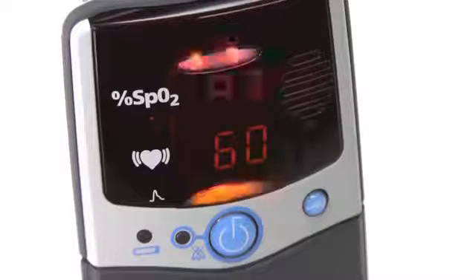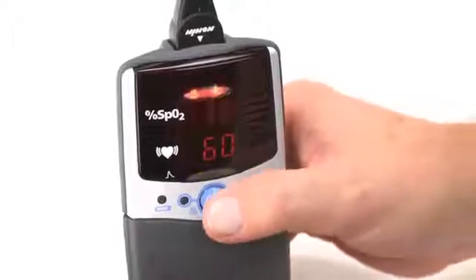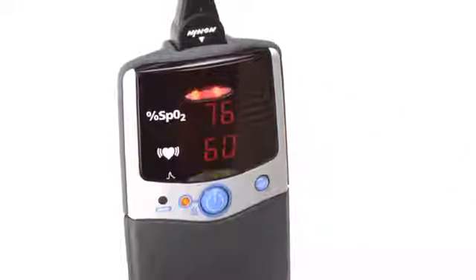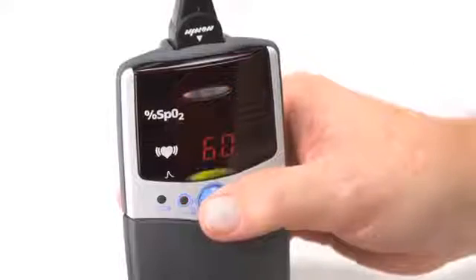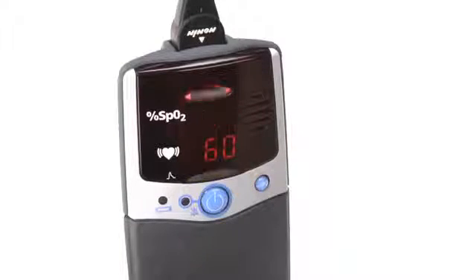For the 2500A model, your oximeter has audible and visual alarms that can be set to signal if either oxygen saturation or pulse rate exceed the predetermined ranges. If either of these occurs, the oximeter will sound a 3-beep, 2-beep audible signal that will repeat every 10 seconds. The condition that is out of range will flash. You can silence the audible alarm for 2 minutes by momentarily pressing the on-off button, and you can return the audible alarm by momentarily pressing the on-off button again. When oxygen level or pulse rate return to the preset range, the alarm will stop and return to normal monitoring function.